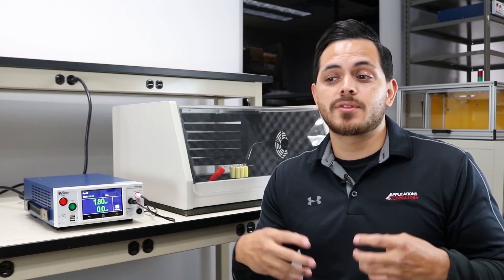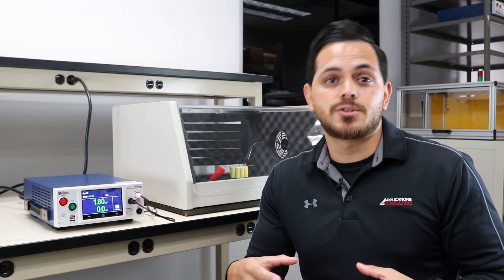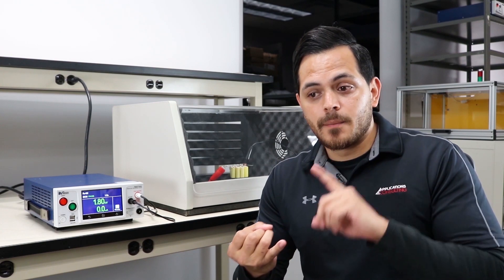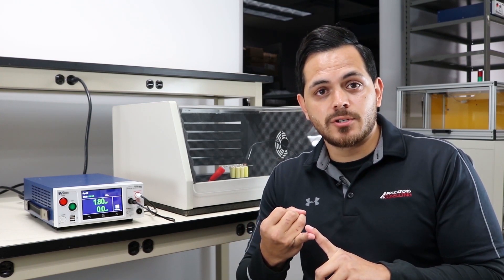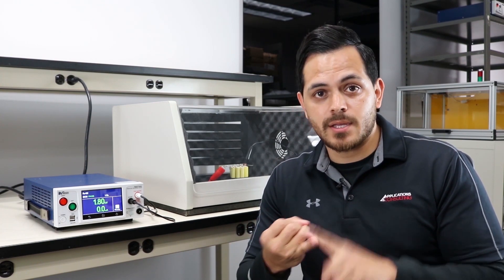So these were the major differences between AC voltage Hi-Pot test and DC voltage. These are the key things you need to remember when choosing which test you're going to run. Understanding the capacitive nature of your DUT - if you don't have it, AC voltage is fine.